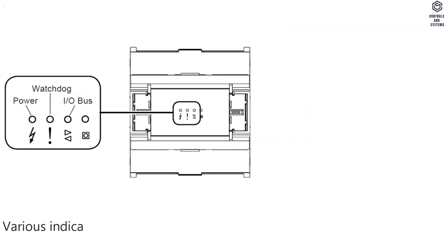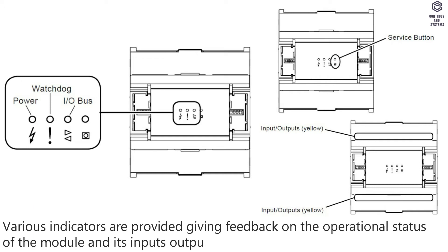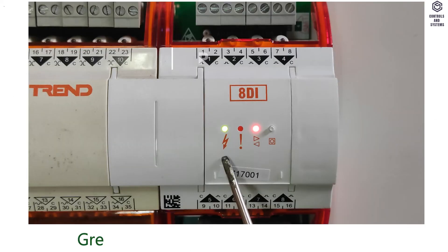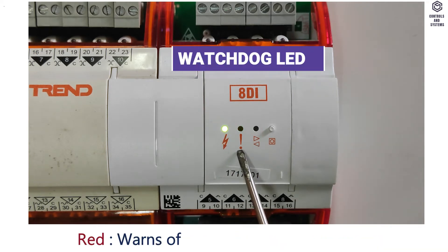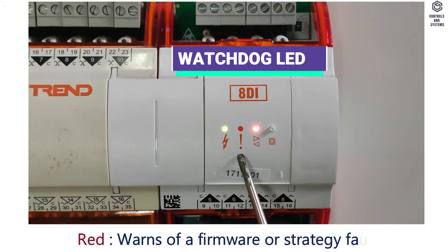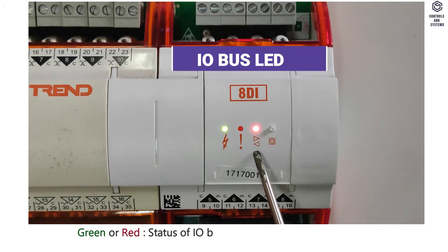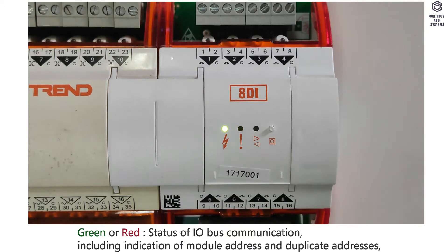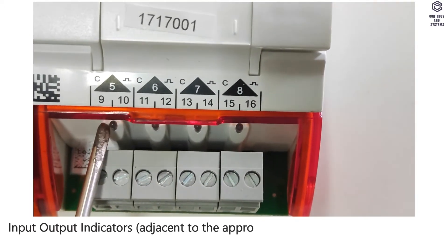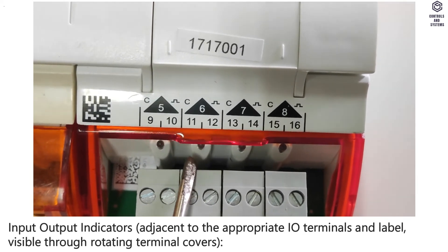Indicators: various indicators provide feedback on the operational status of the module and its inputs/outputs. Power LED glows green — indicates condition of input power supply. Watchdog LED glows red — warns of a firmware or strategy fault. I/O bus LED glows green or red — indicates status of I/O bus communication, including module address and duplicate addresses.